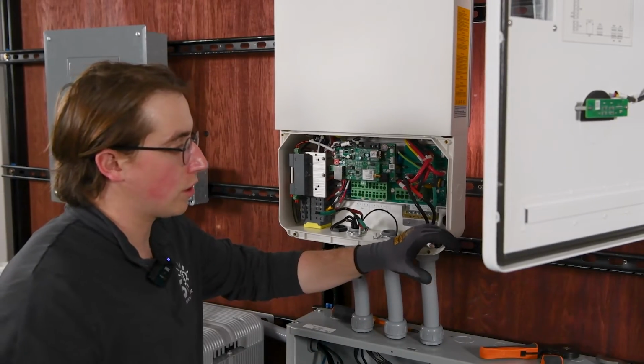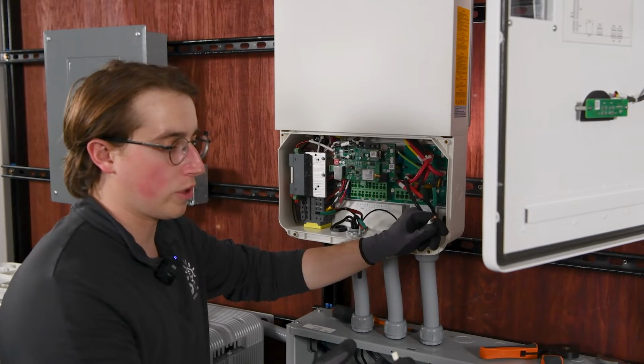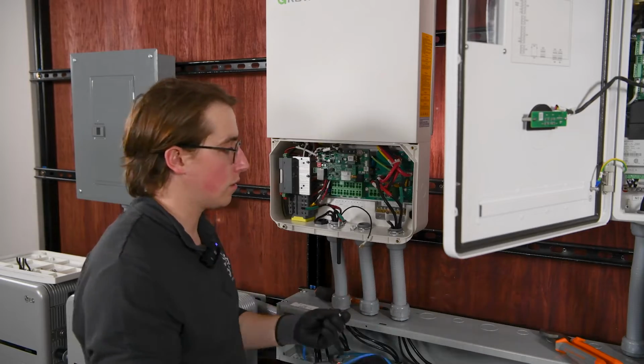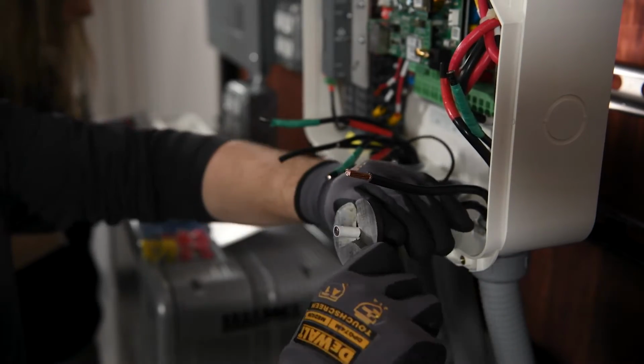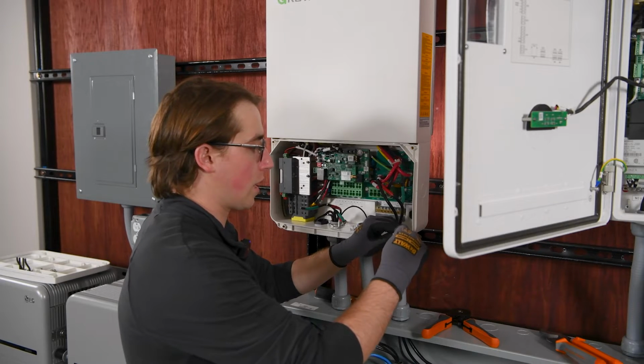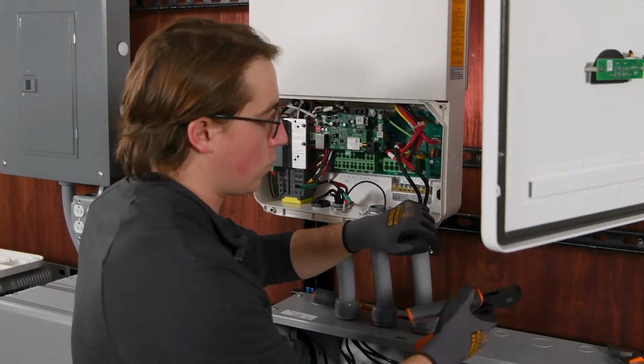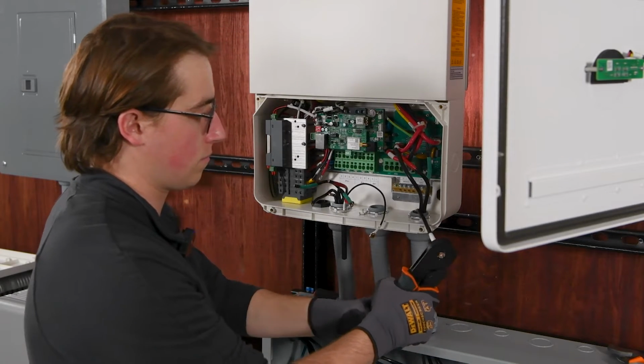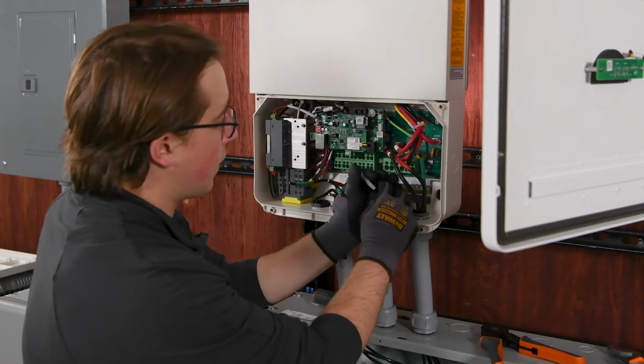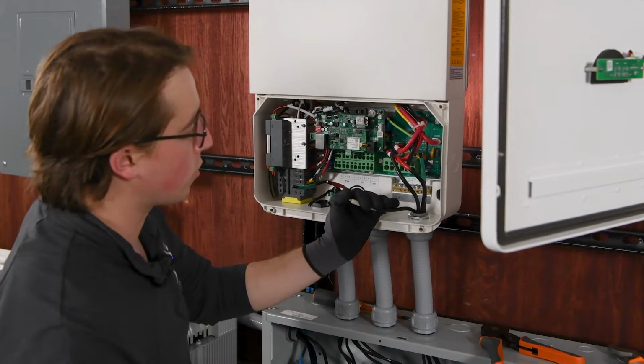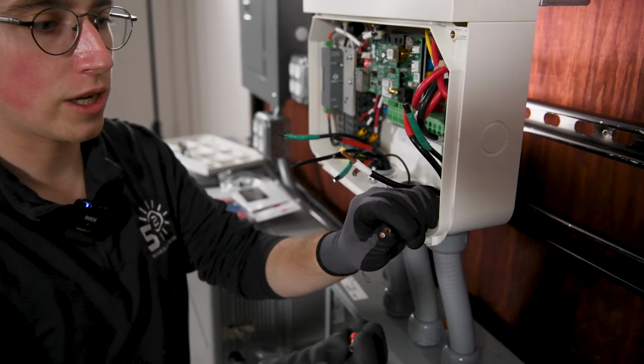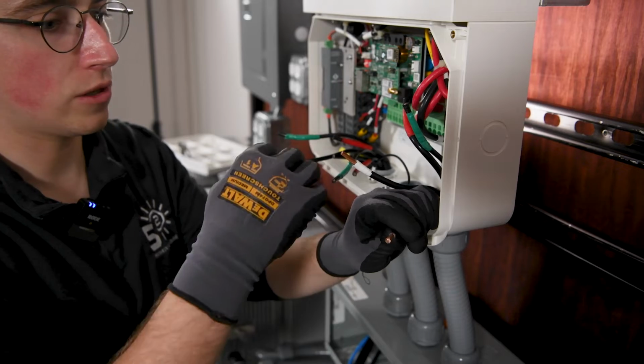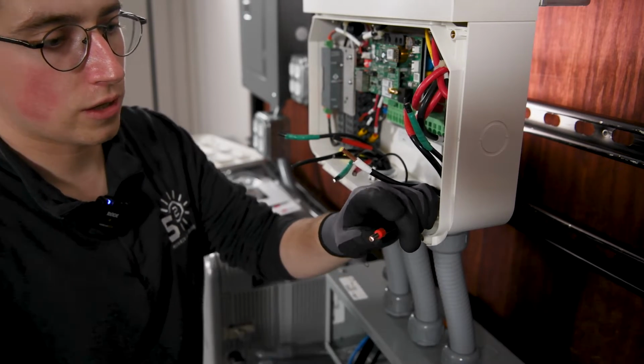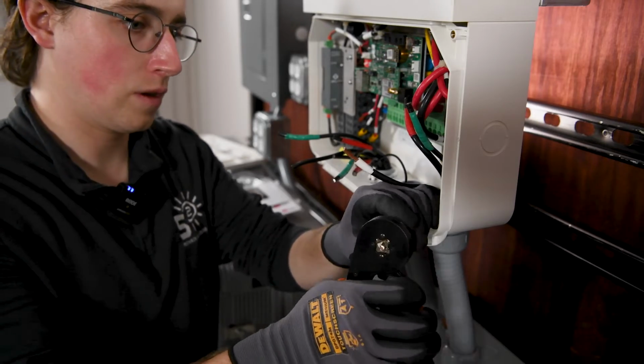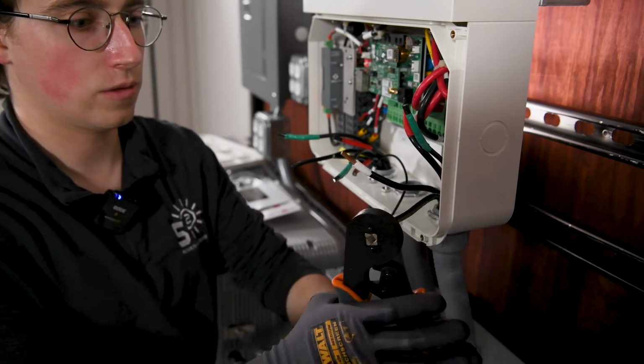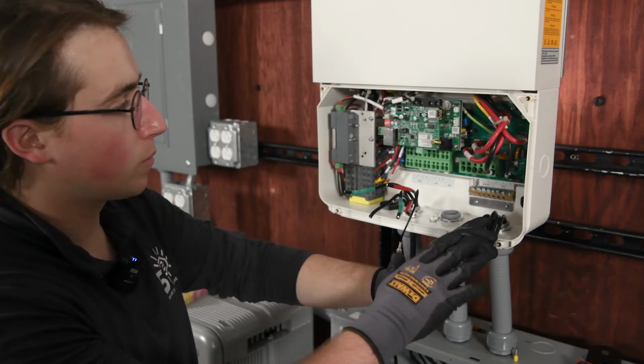So now we're stripping our conductors, or our wires, and we are going to put ferrules. And if you have a crimping tool set, then this will work out just perfectly for you. Just go ahead and strip our conductors to the right length, and we'll attach our ferrule on the end here, and then we'll crimp it. Just like that. Now that's going to allow us to get a secure connection inside this terminal block. Highly recommended that you get a ferrule set to ensure that all these strands stay connected when entering the terminal block. So here we're just going to connect our ferrule, take our crimper, make sure that all those wires stay nice and connected.